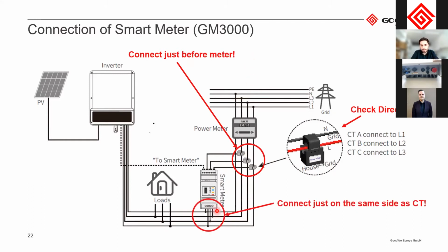Also, for the voltage sense, it's important to connect it on the same side as the CTs. So the voltage sense should not be connected here before, otherwise the readings will be wrong. They should be connected ideally as close as possible to the CTs, but just make sure that there are no loads in between the voltage sense and the CTs.